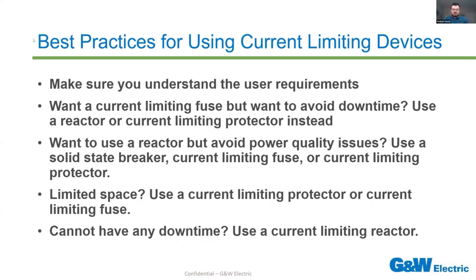Say they want to use a reactor, but are worried about the power quality issues. It might be worth then investigating using a solid state breaker, current limiting fuse, or current limiting protector as a result. All devices that are going to avoid that added impedance that a reactor would add to your system and cause those power quality issues. If they have limited space, but they want that current limiting device, you want to steer them towards using a current limiting protector or current limiting fuse instead. They might be worried about it having any kind of downtime at all. In that case, your best option would be a current limiting reactor, because once again, it passively continuously operates, and there's no risk of it going down unless something's wrong with the reactor itself.